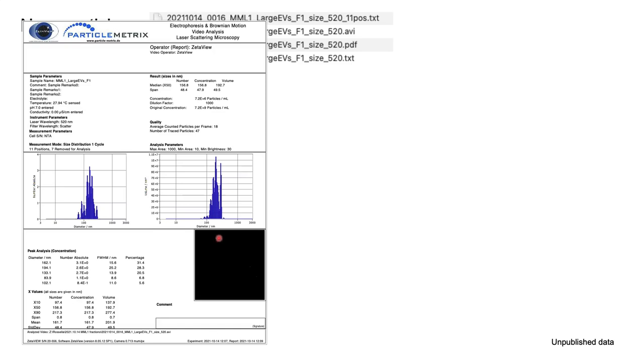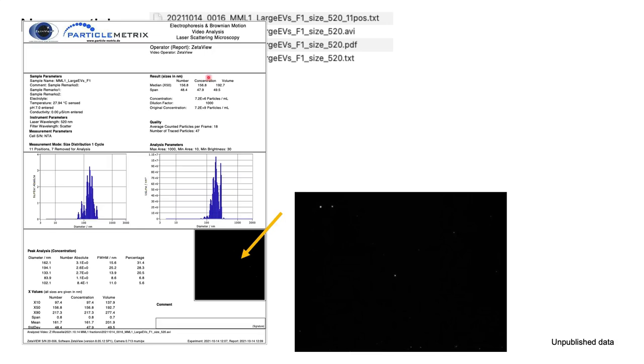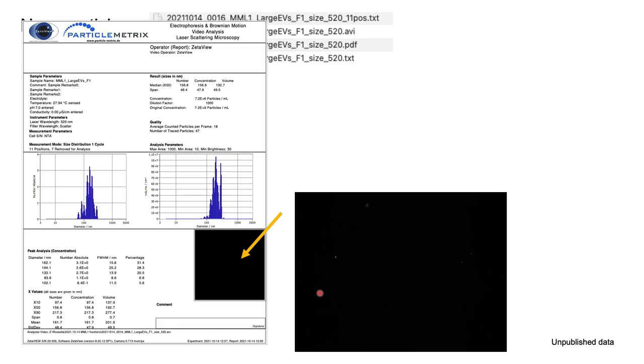Looking at the PDF file, you can notice that here there are no particles — but still you have the concentration of particles, and it's a quite good concentration. If you look at the video, you can see that here there is nothing, here there is something, and then nothing or just a few particles. The machine counts 11 positions and it can be that some positions are not good — the machine is dirty or something is going wrong. The message is: you still have the number of particles and you are happy about it, but these numbers in this case are not believable.